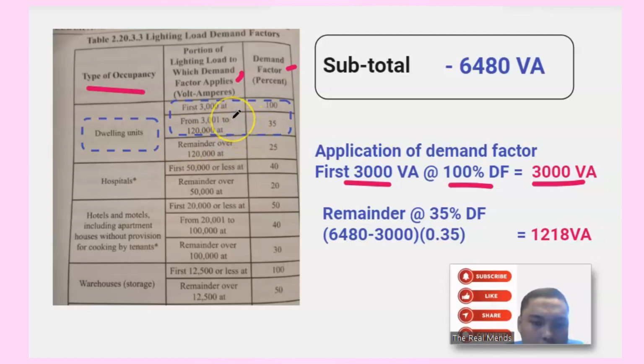And then from 3,001 to 120,000 at 35% demand factor. So yung 6,480, let's deduct the 3,000. So that is yun na yung remainder niya at 35% demand factor.